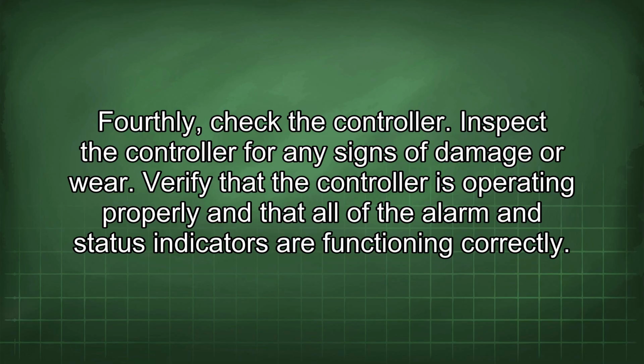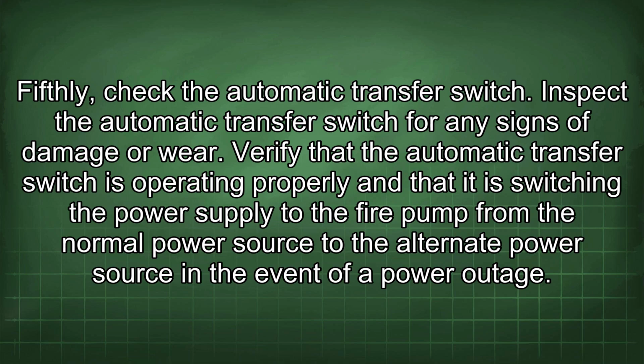Fourthly, check the controller. Inspect the controller for any signs of damage or wear. Verify that the controller is operating properly and that all of the alarm and status indicators are functioning correctly. Fifthly, check the automatic transfer switch. Inspect the automatic transfer switch for any signs of damage or wear. Verify that the automatic transfer switch is operating properly and that it is switching the power supply to the fire pump from the normal power source to the alternate power source in the event of a power outage.